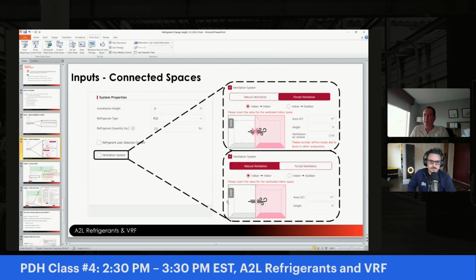Looking at connected spaces, you have another option for mitigation controls being ventilation — they can be indoor to indoor, indoor to outdoor, current — there are several ways to do it. If you're ventilating to a neighboring indoor unit space, you'll input the area and height of that zone, and for mechanical ventilation, you'll also need to input your airflow rate, CFM, here.